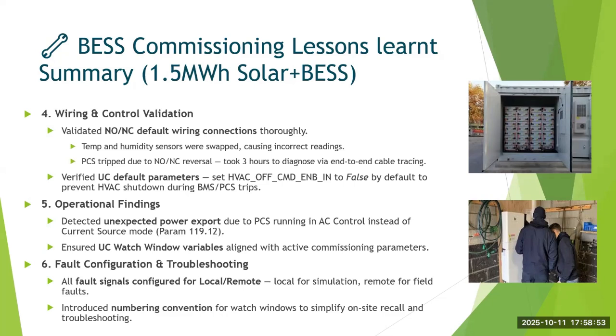Also, for the fault conditions, we need to have local and remote. We should have field signals properly so that when any fault occurs, we know which fault it is. Is it a PMU fault, a PCS fault, a PCS hardware fault, are the contactors malfunctioning, or is the fire panel malfunctioning? So we need to have all the fault signals, both local and remote. In case the hooter keeps hooting from the fire panel and no one is there, or someone locally sees the fire panel hooting but nothing is happening, we should have local control and see what is happening. So local and remote controls are equally important for troubleshooting.